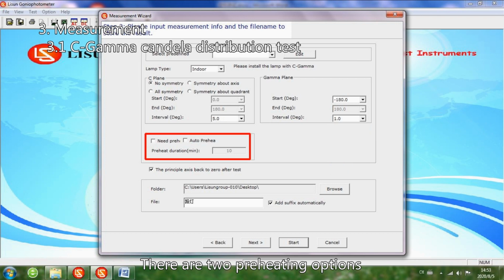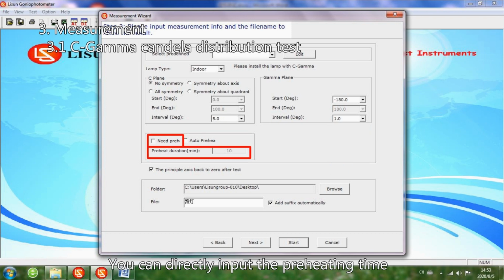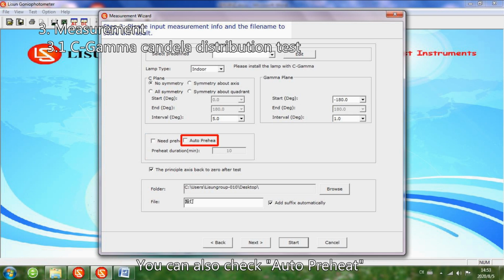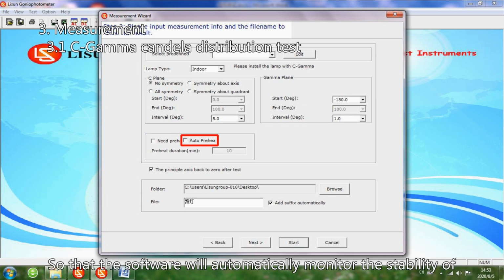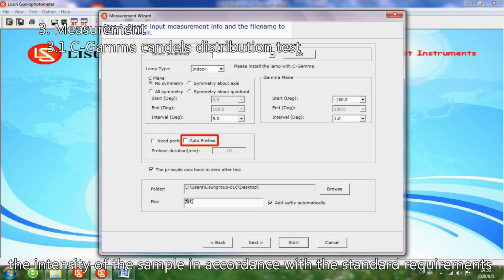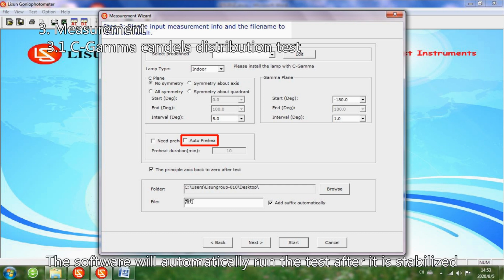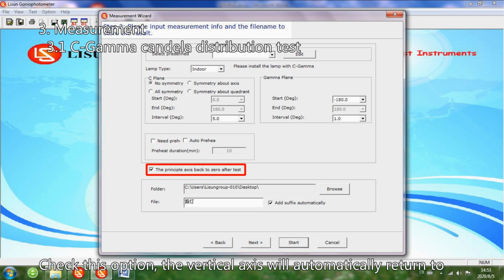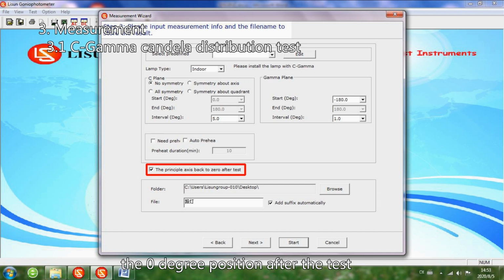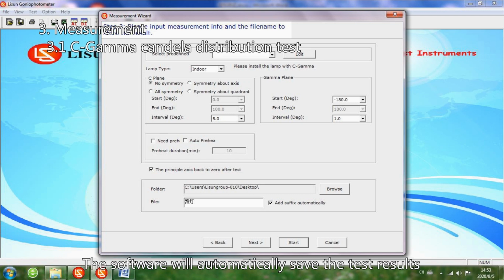There are two preheating options. You can directly input the preheating time. You can also check auto preheat. So the software will automatically monitor the stability of the intensity of the sample in accordance with the standard requirements. The software will automatically run the test after it is stabilized. Check this option, and the vertical axis will automatically return to the 0 degree position after the test. The software will automatically save the test results.